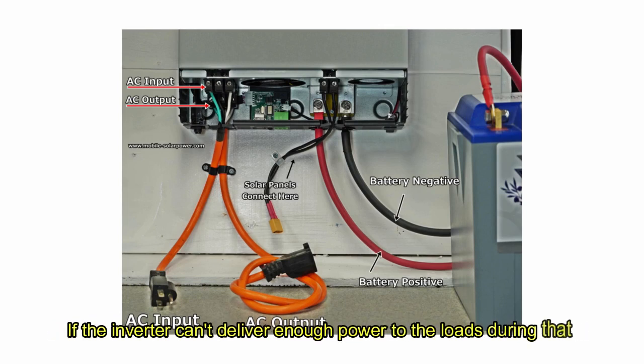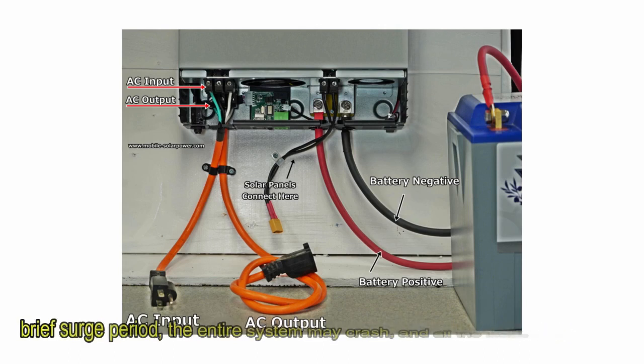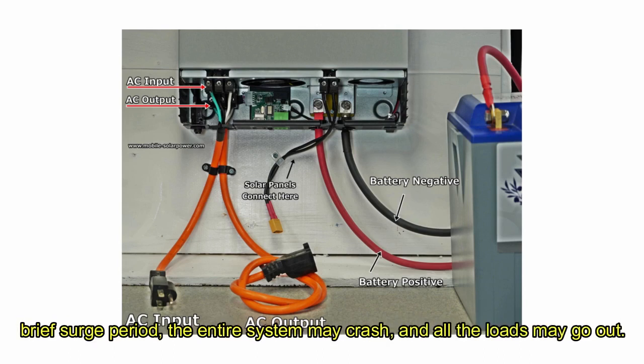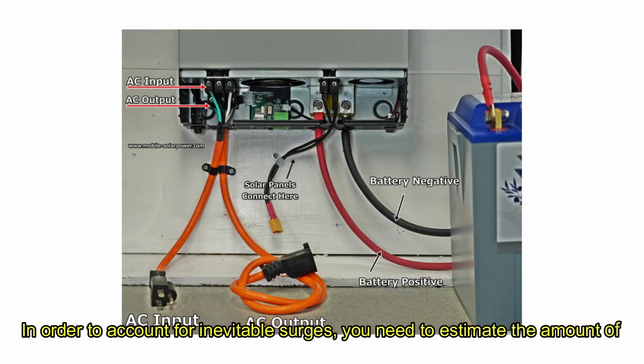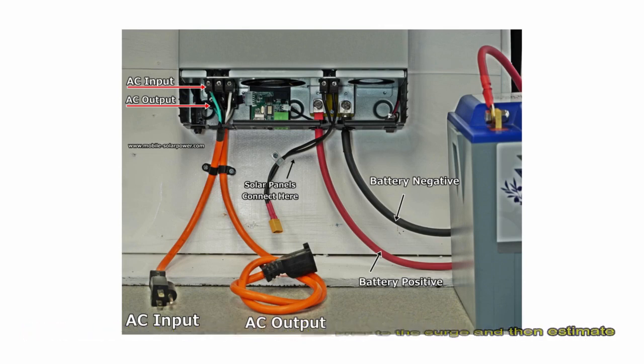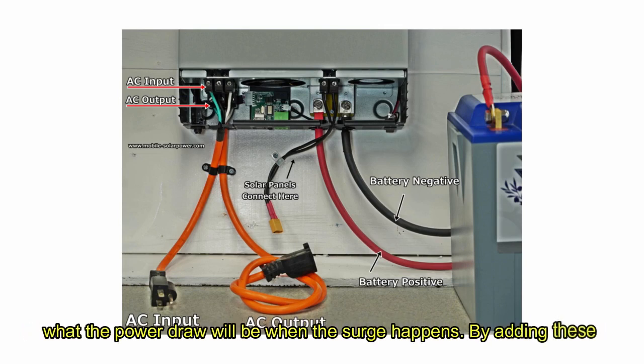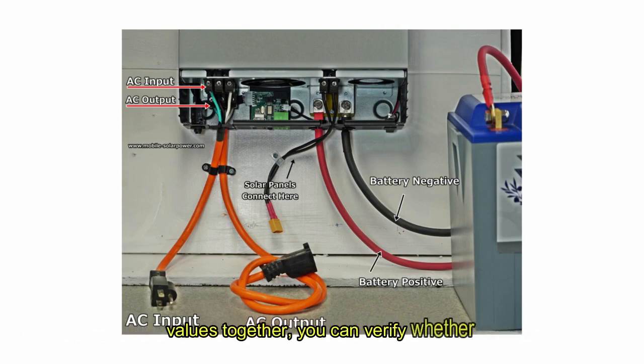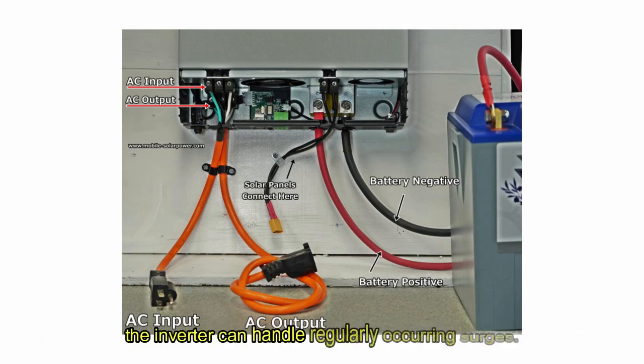If the inverter can't deliver enough power to the loads during the brief surge period, the entire system may crash and all the loads may go out. In order to account for inevitable surges, you need to estimate the amount of power the inverter will be providing just prior to the surge, and then estimate what the power draw will be when the surge happens. By adding these values together, you can verify whether the inverter can handle regularly occurring surges.